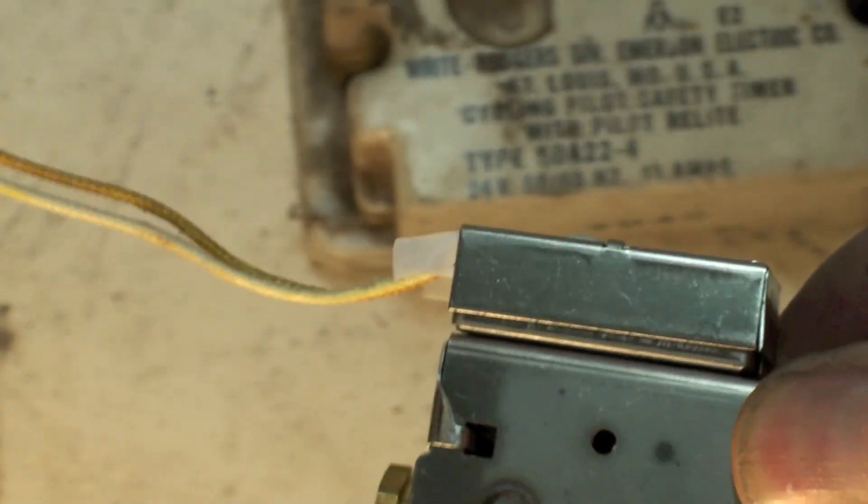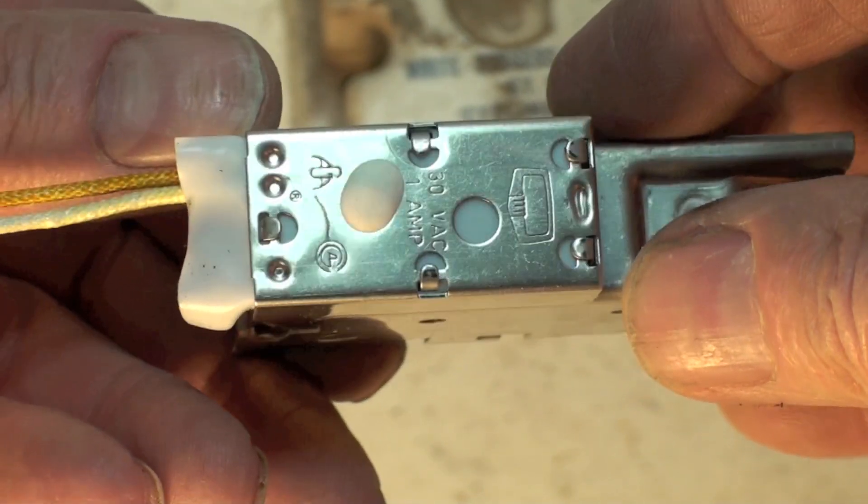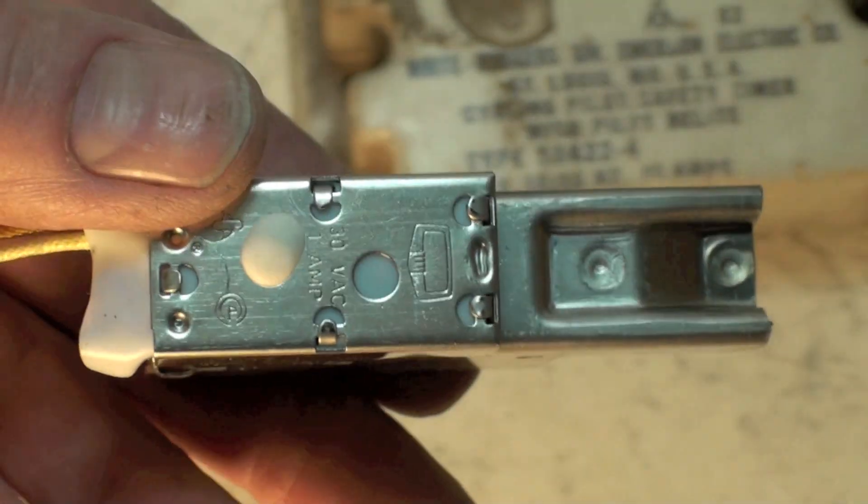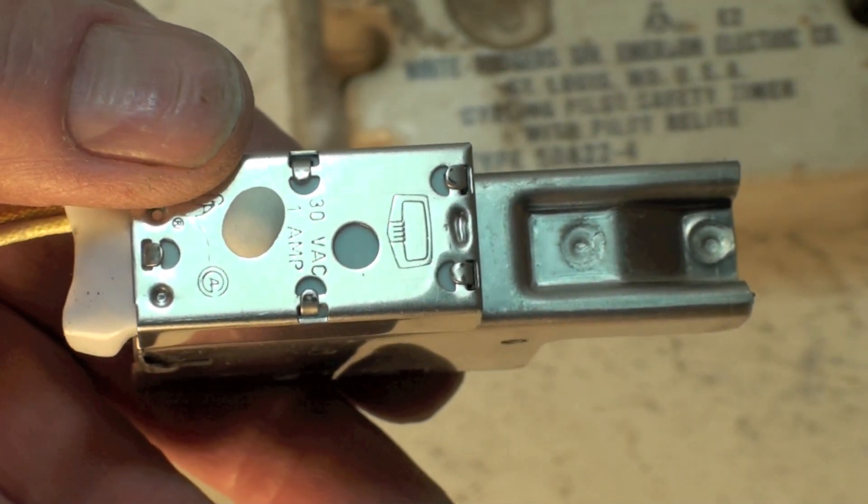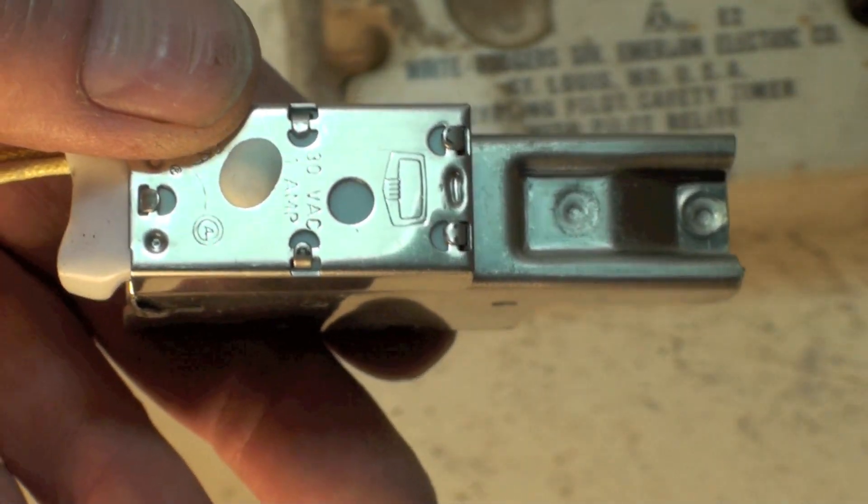This switch here where these wires are is a normally open switch. If there's no pilot then this thing is open. When the pilot's on it closes and allows main gas to come on.